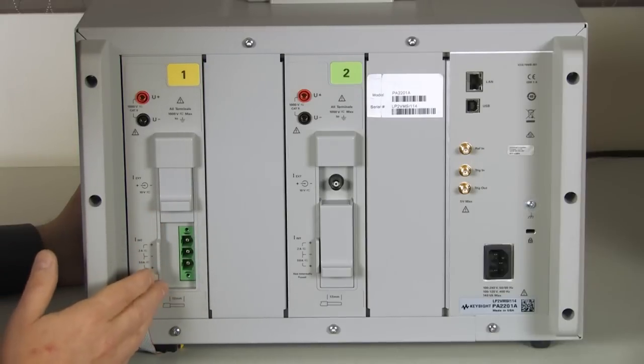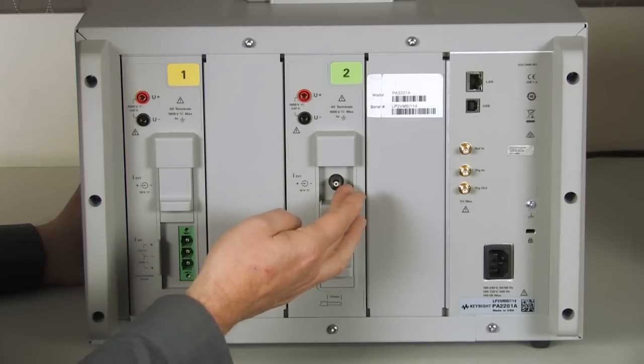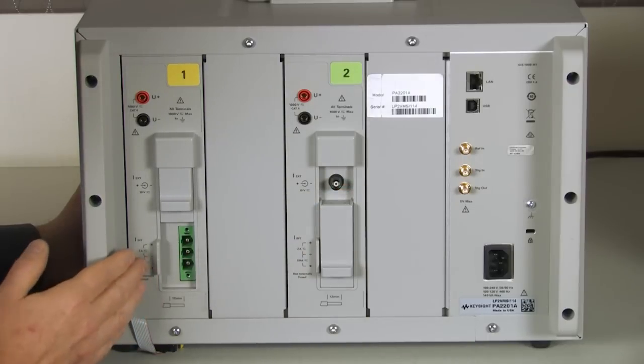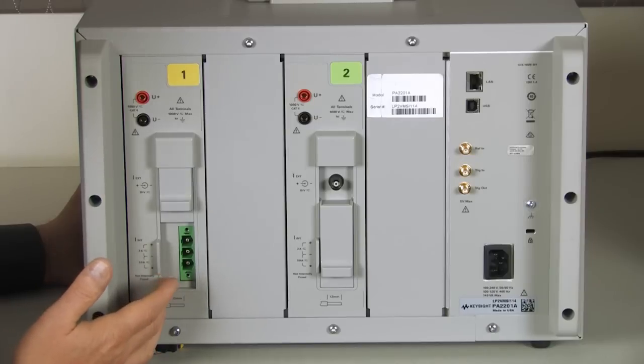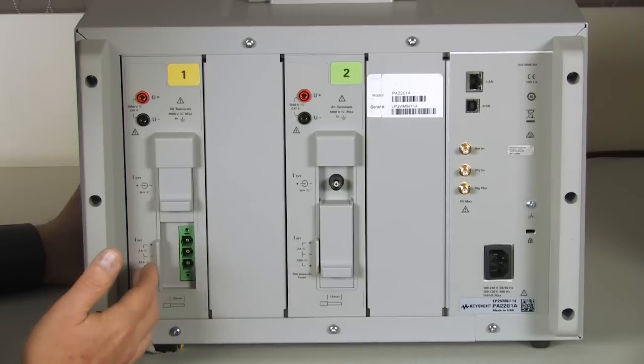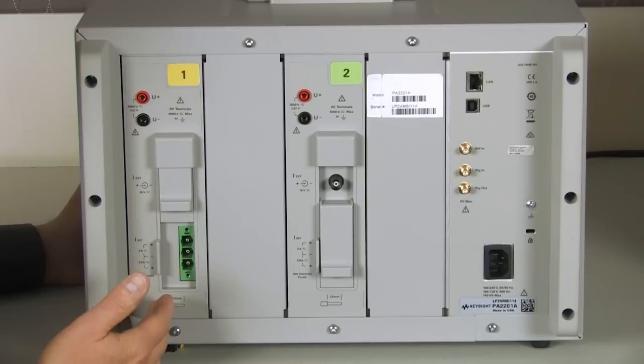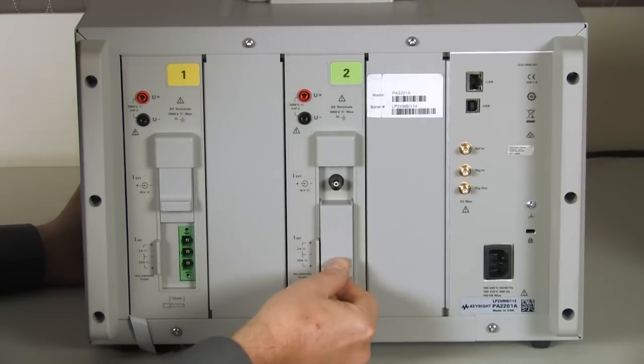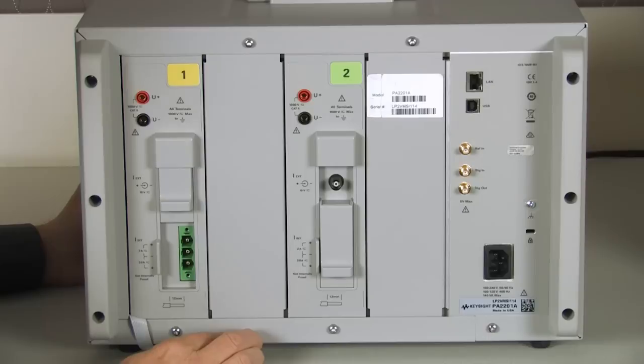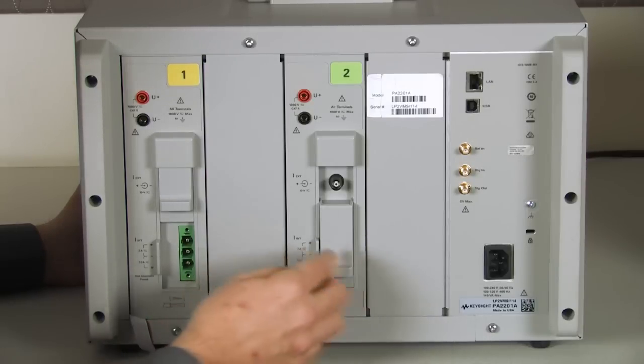The current connections come in two varieties, either our direct connection or a BNC connection for external probes. The direct connection has both a 2 amp and a 50 amp connection. Then those go through a shunt that's built into the system. If you have currents that are higher than the 50 amps, you'll move the slide down and you'll expose the BNC connector for the external probes.